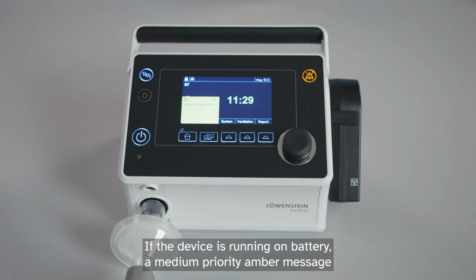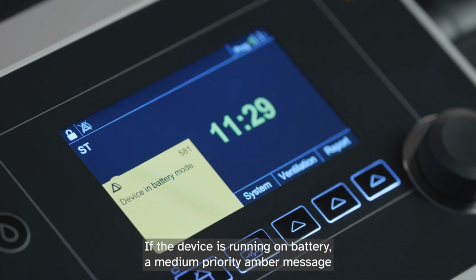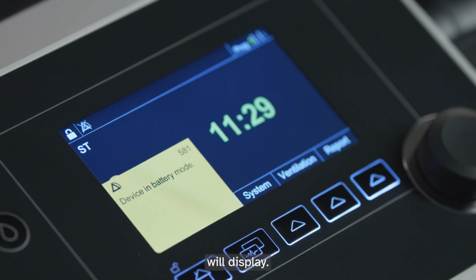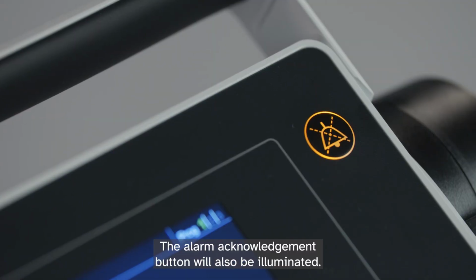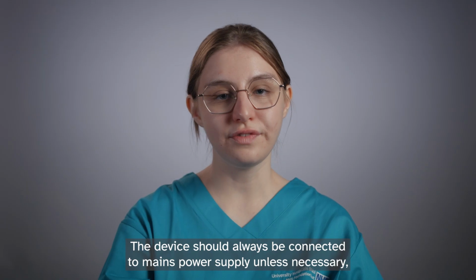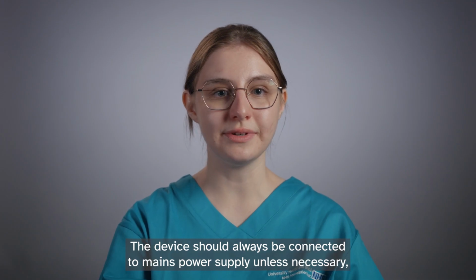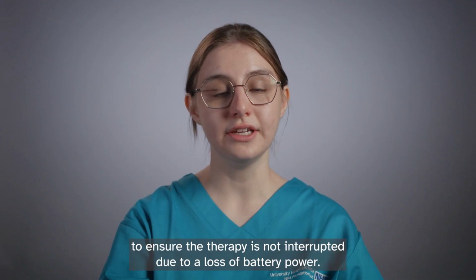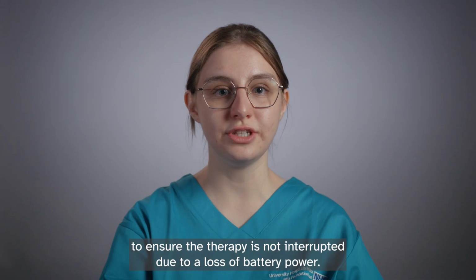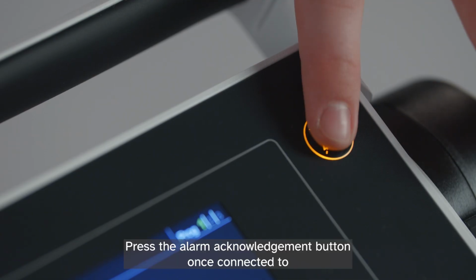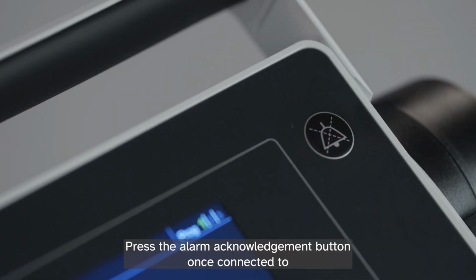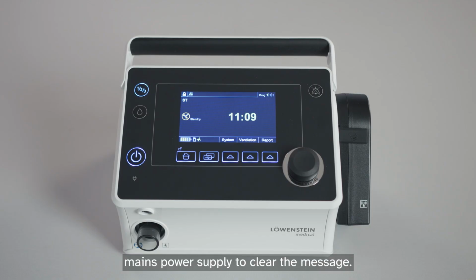If the device is running on battery, a medium priority amber message will display. The alarm acknowledgement button will also be illuminated. The device should always be connected to mains power supply unless necessary to ensure therapy is not interrupted due to a loss of battery power. Press the alarm acknowledgement button once connected to mains power supply to clear the message.